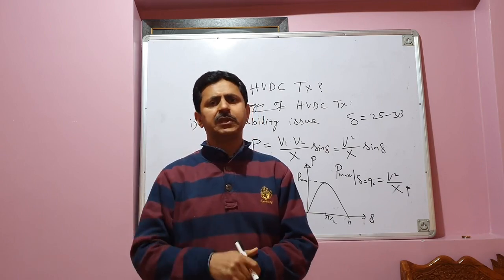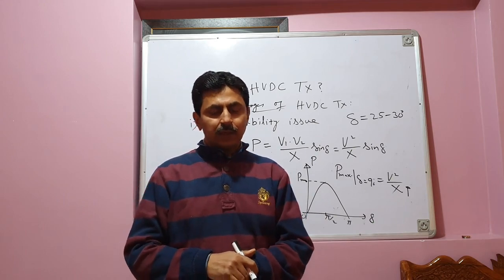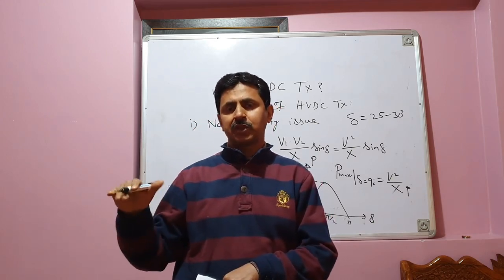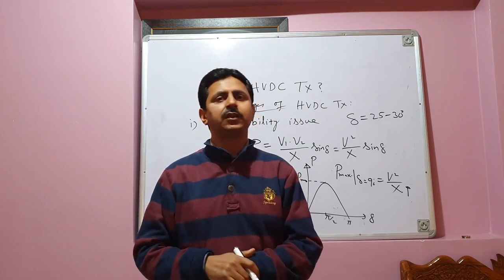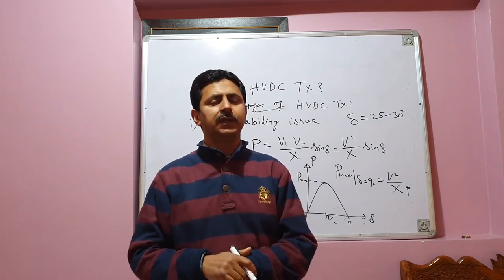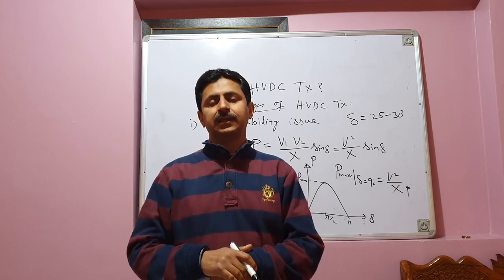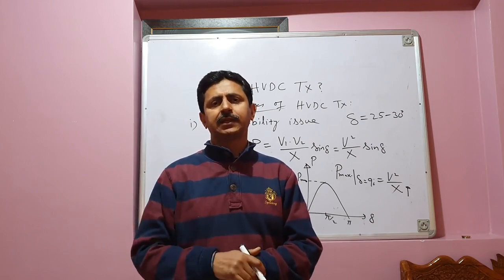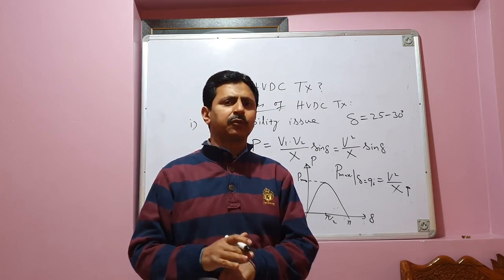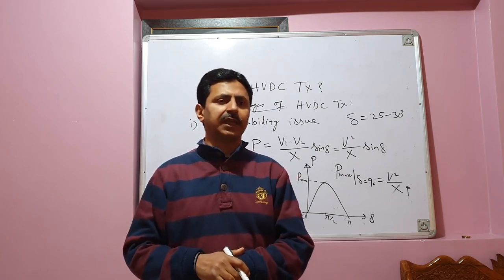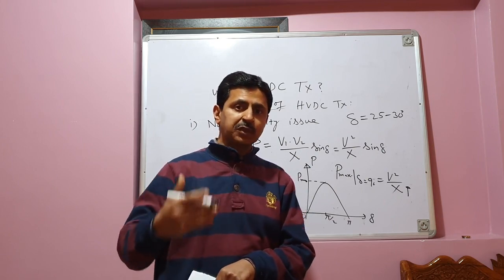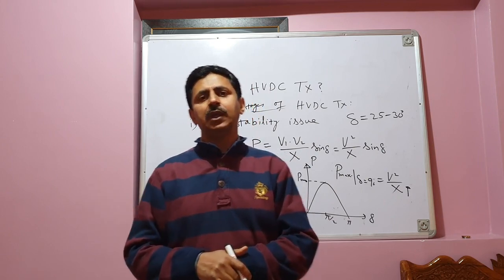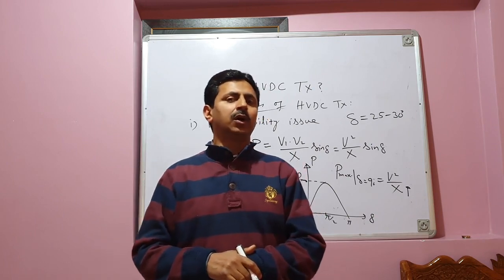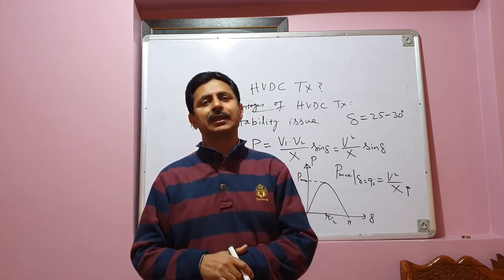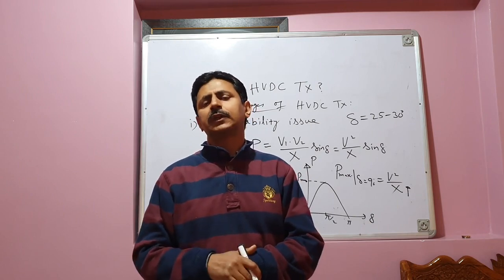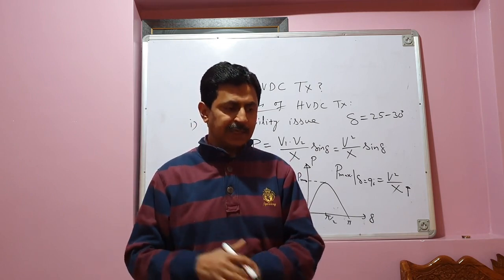And again, there will be stability issues, which means that a power transmission line which has the capability of transmitting a certain amount of power, we are not able to fully utilize it. We operate it at a very low value of delta, say 20 to 30 degrees, and therefore we are not fully utilizing the capacity of the line. The line has the capability of transmitting more power, but because of the stability issues, we are not able to operate the system at delta equal to 90 degrees, and therefore the line remains underutilized in a way.